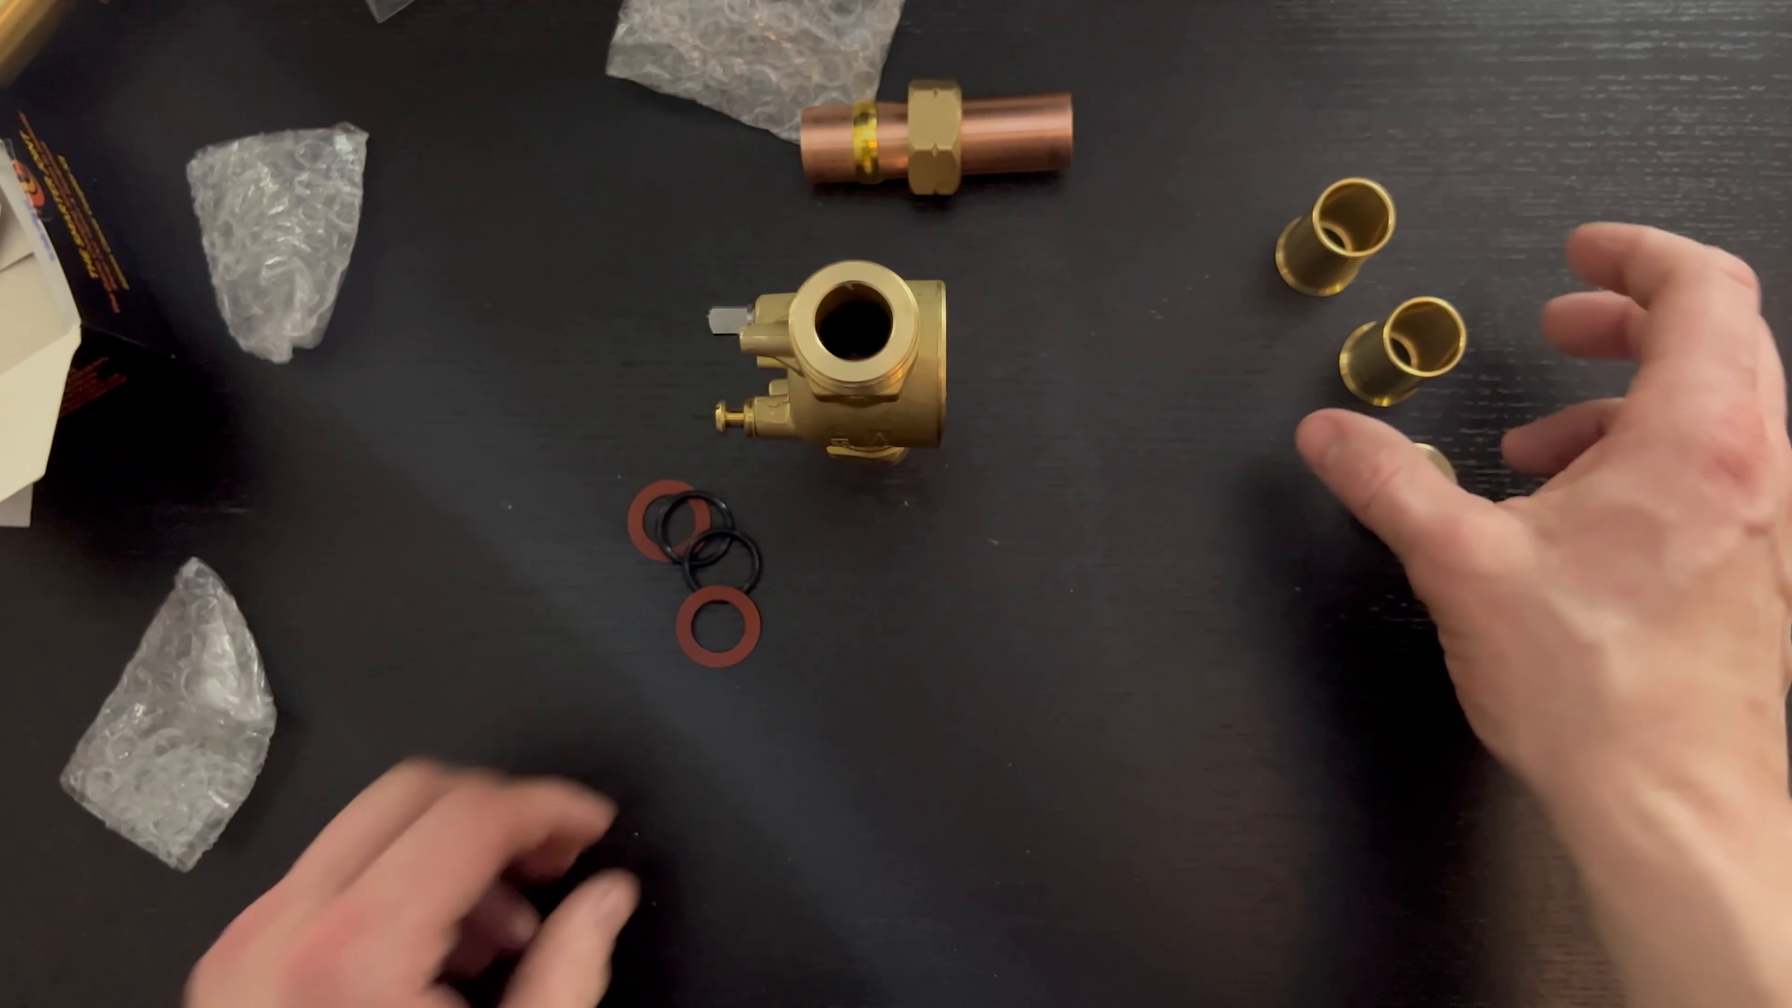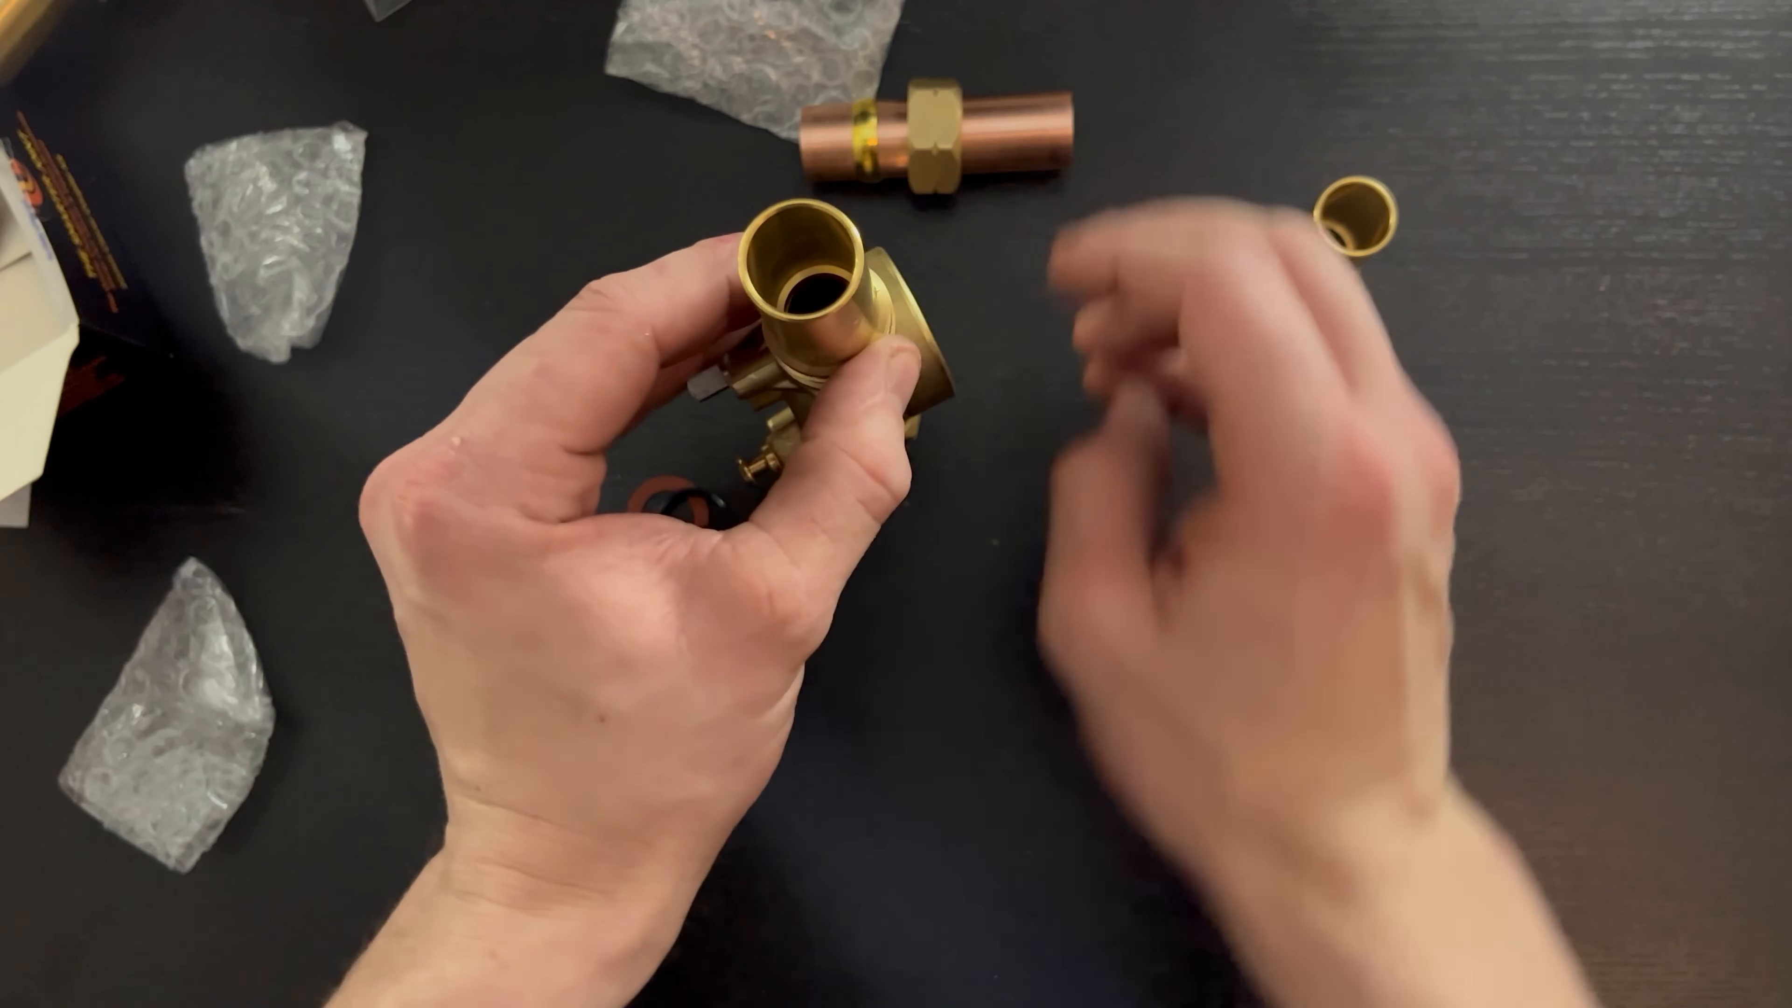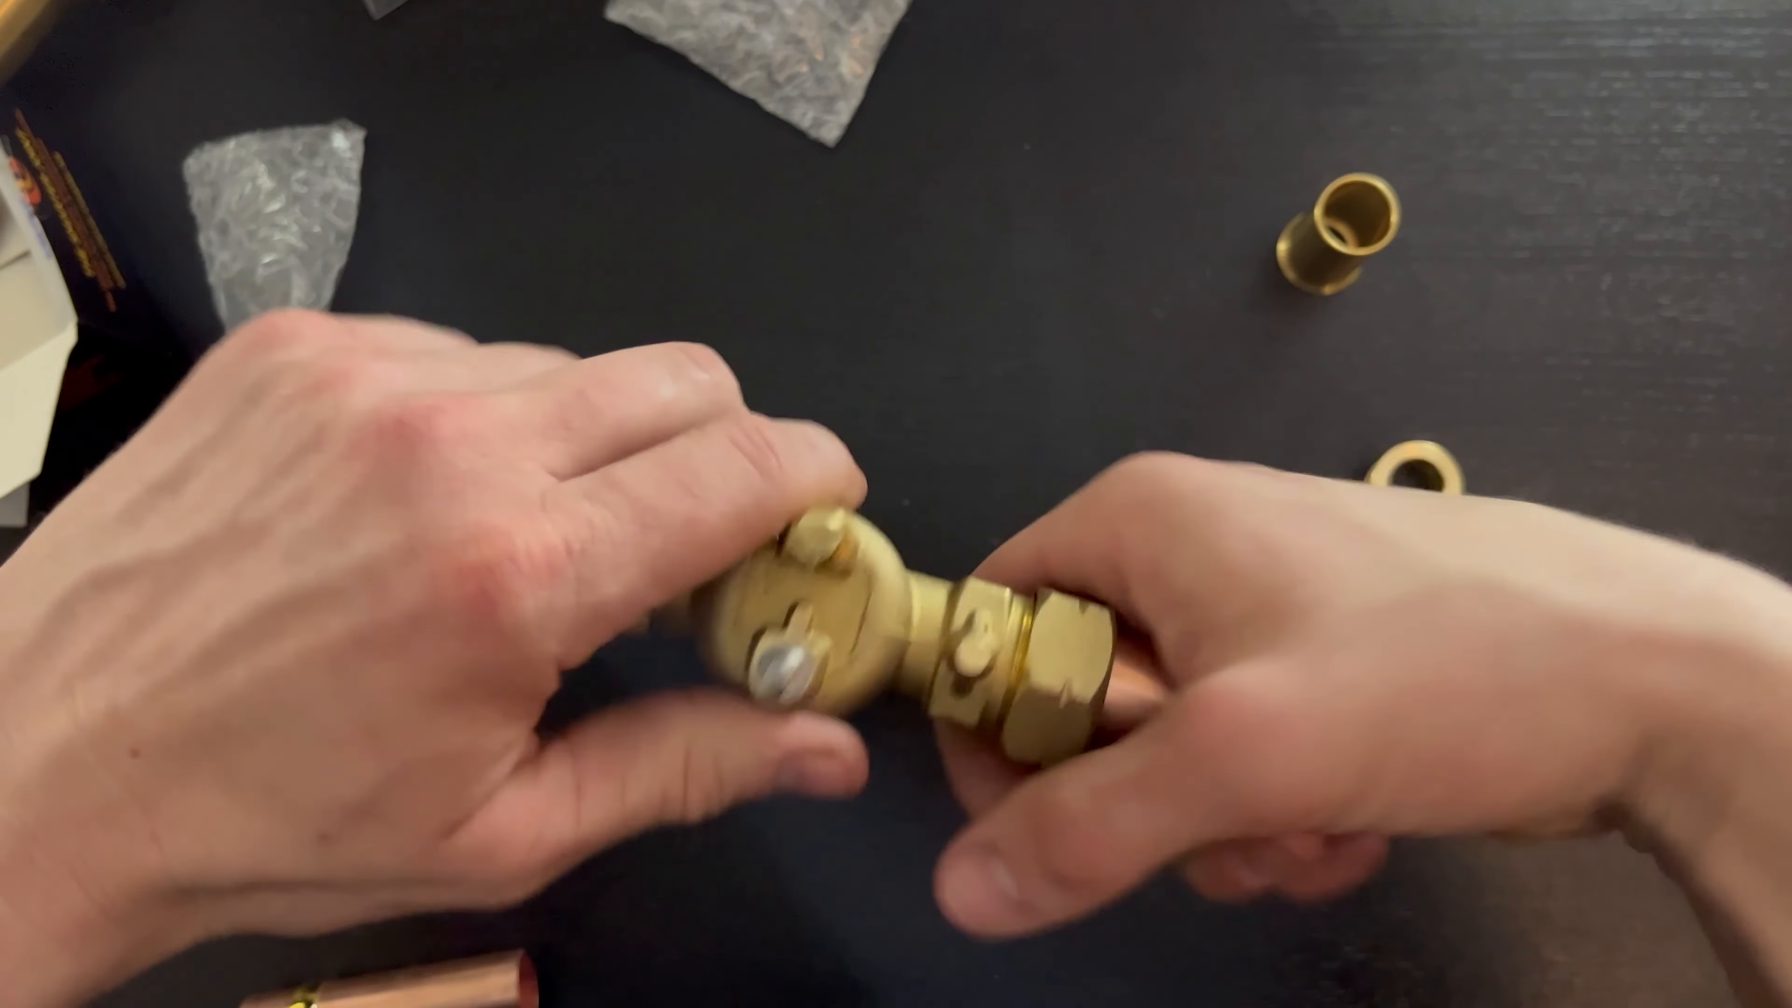After you've put your insert adapter in, take one of your fibre washers, take one of your stub adapters and then get the nut that came with the valve, slide it over and tighten. Repeat for the other end.